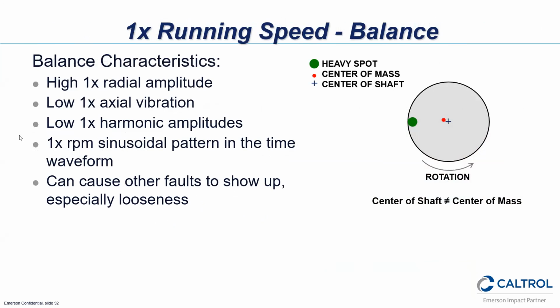So here's a typical imbalance. Basically, it happens at 1 times rotational speed. So as I said, RPM or CPM, this will be at the actual rotation of the fan. Basically, when you're seeing a high amplitude, there's a heavy spot on the fan wheel itself that's rotating around, and we're catching that, which is creating the movement in the unit.